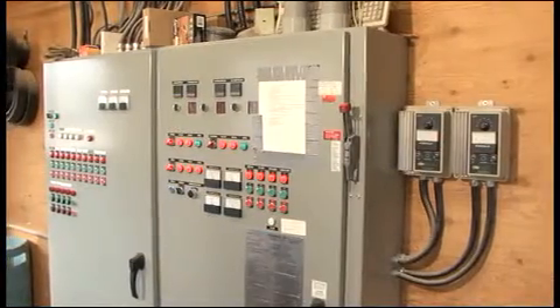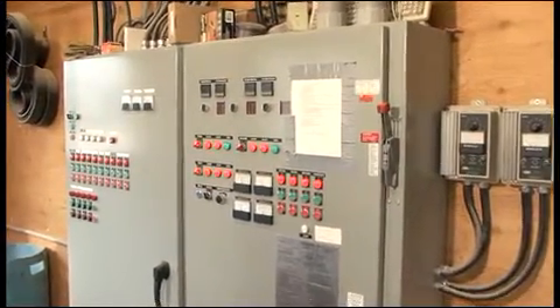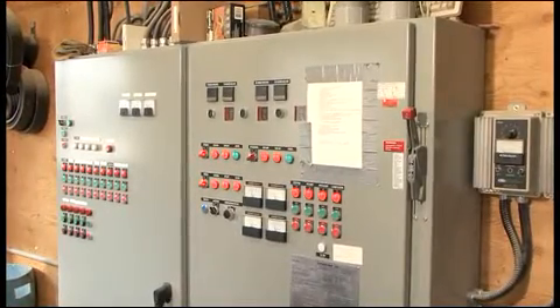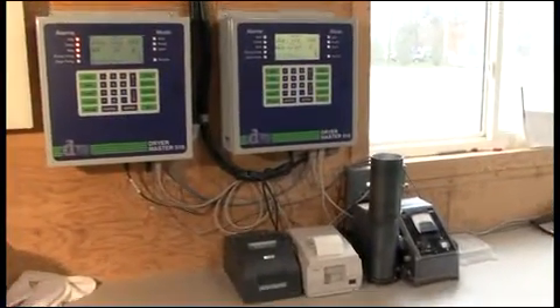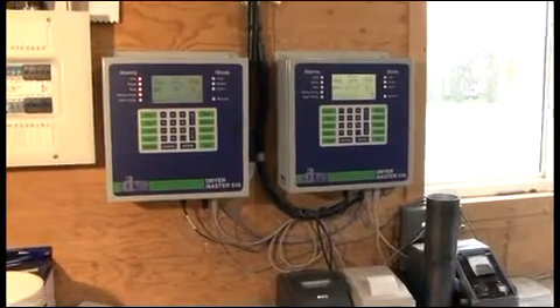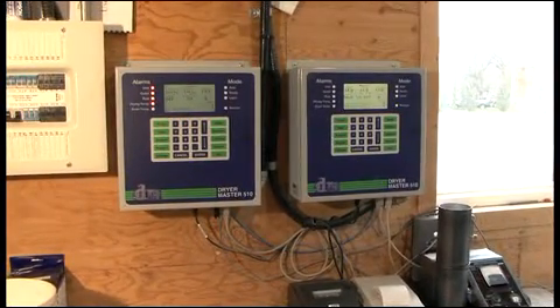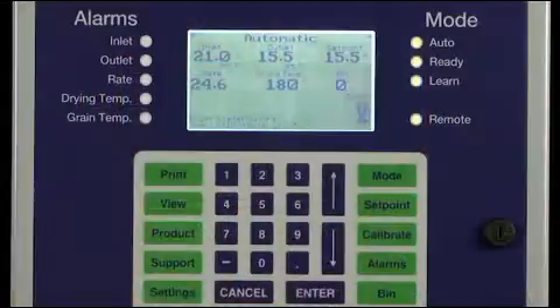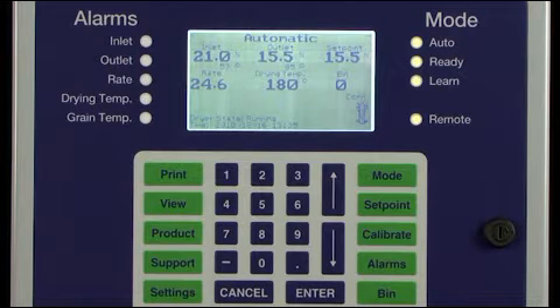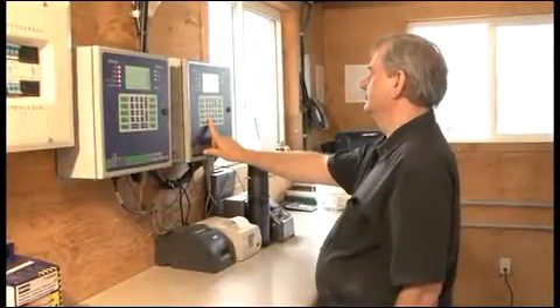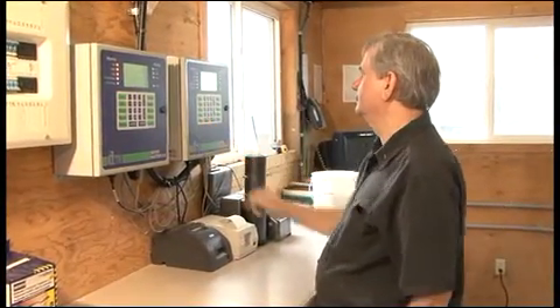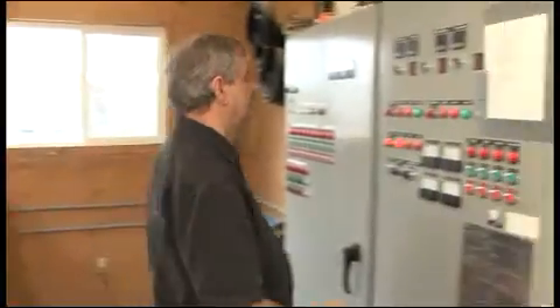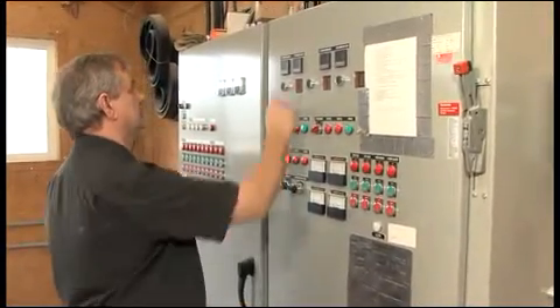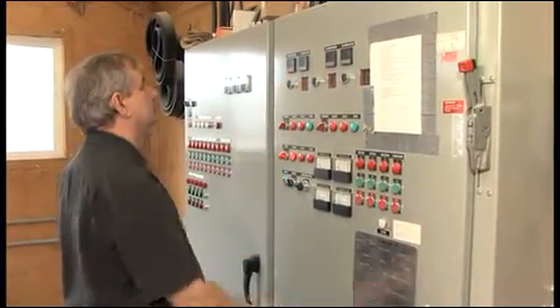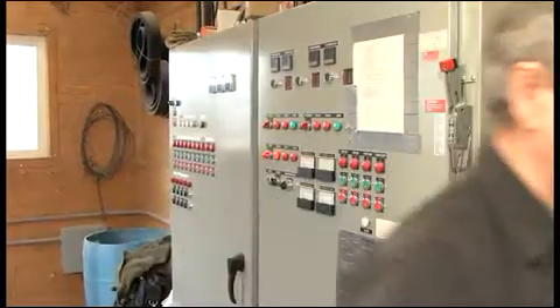The Dryer Master 510 interfaces with your dryer by a connection to your dryer discharge system. With the Dryer Master in local, your dryer operates as it did prior to the installation of the Dryer Master. With the Dryer Master in manual or automatic mode, it sends a set point to the discharge system to operate the dryer at the requested discharge rate. As a backup feature, you can always revert to operating your dryer from your dryer panel by setting the Dryer Master to local mode. If the Dryer Master is powered down or turned off, the dryer automatically operates in local mode.